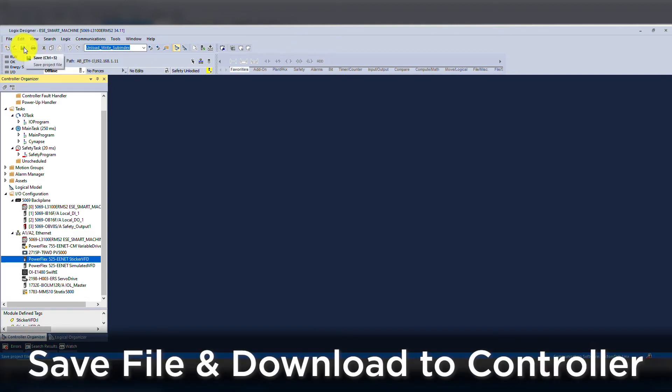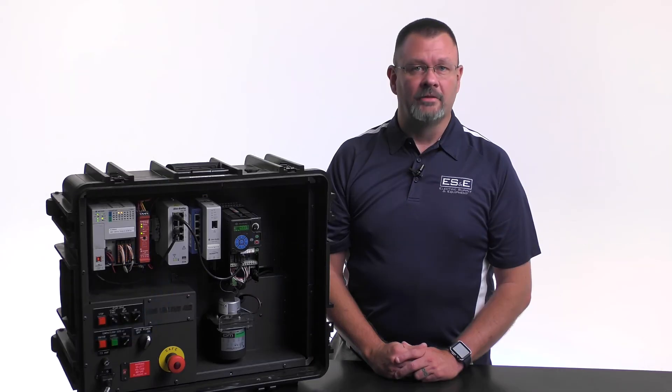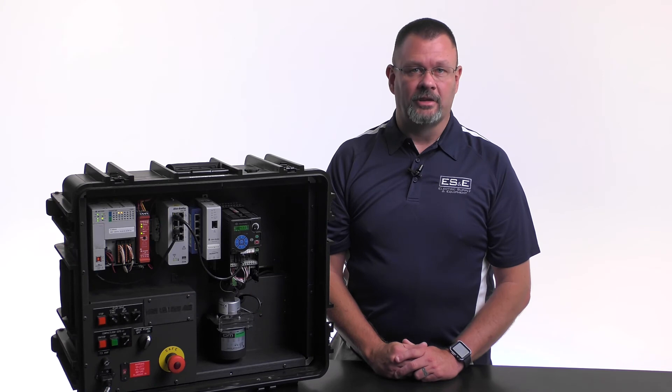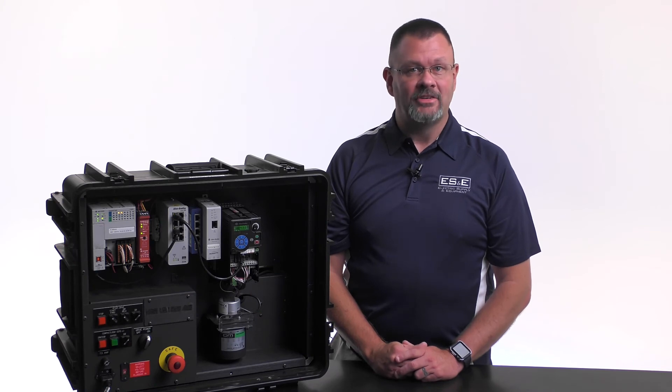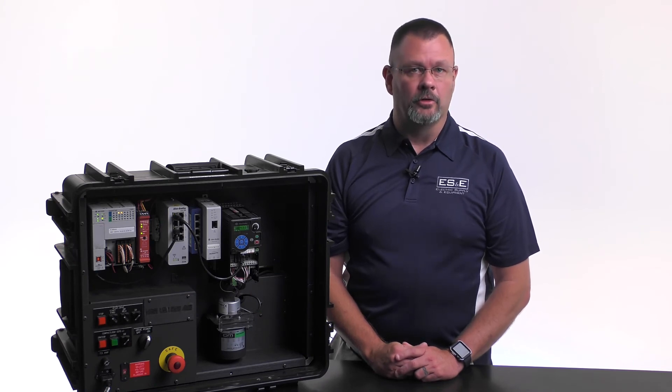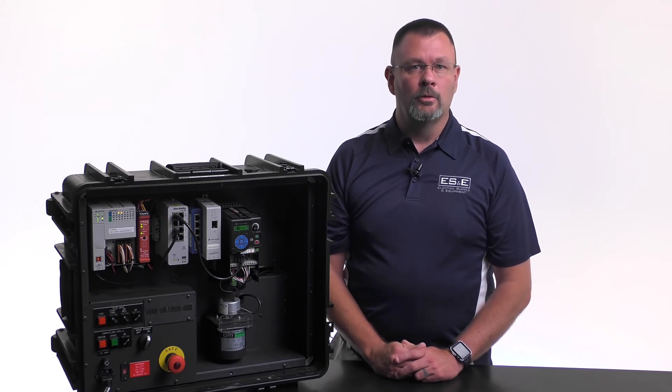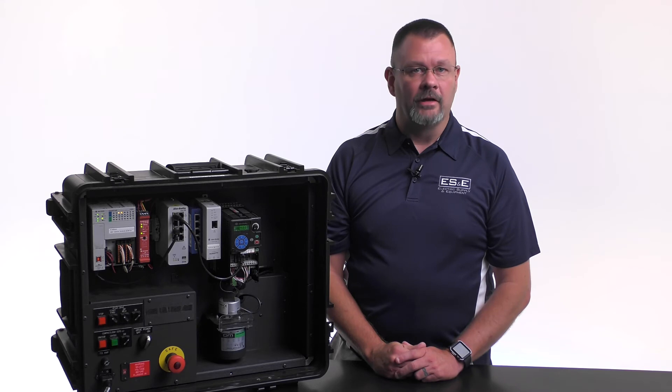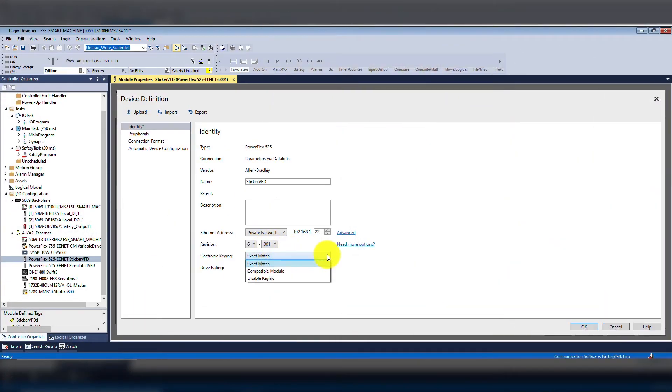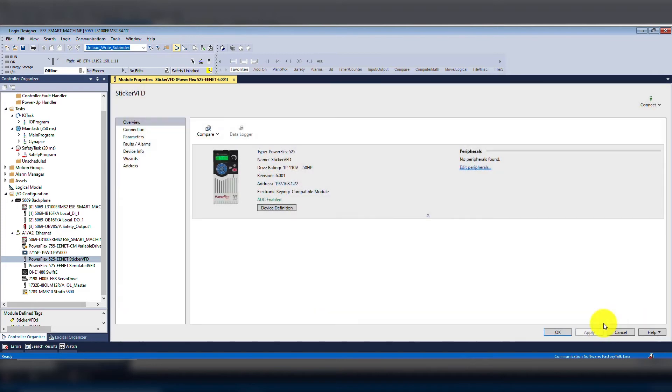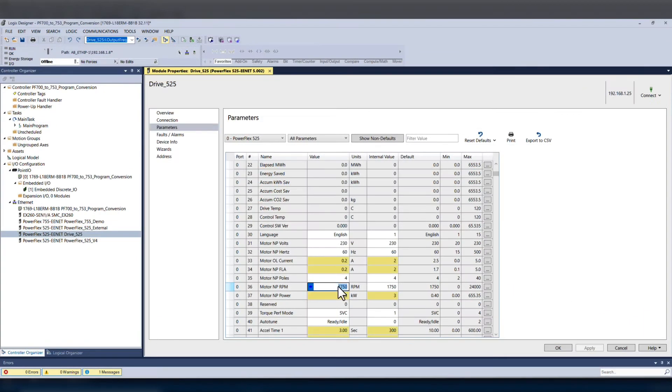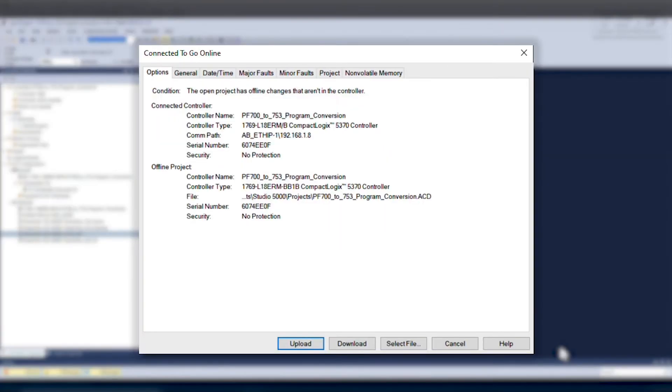It's important to save the ACD file with a new configuration prior to downloading it to the controller. Once the drive is set up for ADC and the ACD file is downloaded to the controller, you will no longer need to download it to make changes. So you can adjust the parameters for the drive while online and then save the file and it will retain those values in the configuration. If someone else has made a change when opening the module properties, it will ask you if you want to use the offline file configuration or device configuration. Depending on the situation, you could choose either option. That's all the configuration needed to set up ADC on a PowerFlex 525.